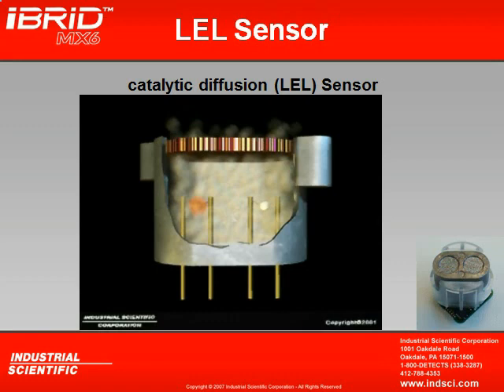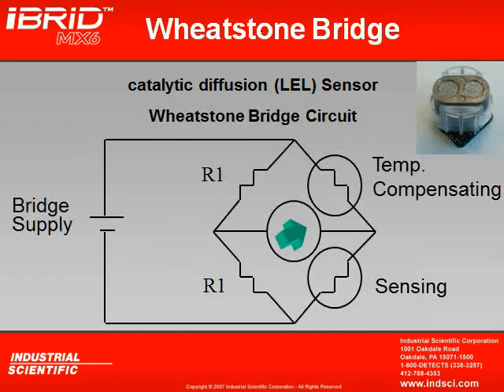How we turn that into a reading is by using something called the Wheatstone bridge circuit. Now when you look at my Wheatstone bridge circuit, you'll see that it is essentially my combustible sensor. I have my temperature compensating bead, and I also have my sensing bead. And inside the instrument are two paired resistors. So we match up the resistance on all four sides of the bridge, and that's what gives you a zero reading on the display of your instrument. It's also known as a balanced circuit.